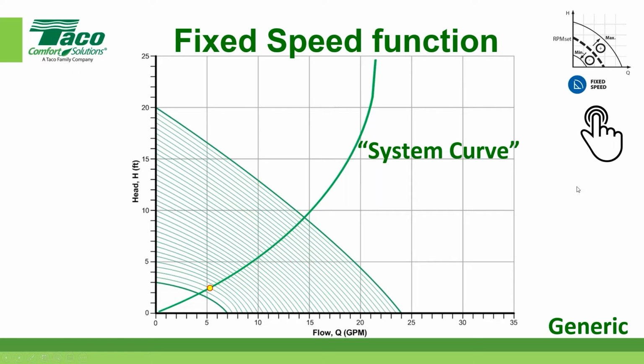This would be what would happen on a single zone application. When we get into multiple zone single system pump applications, remember what changes on the system curve. It's got to move up and to the left. Okay.